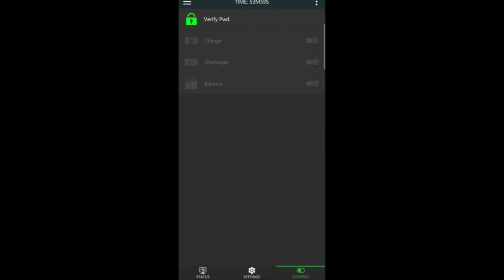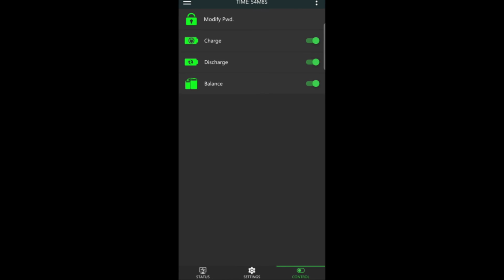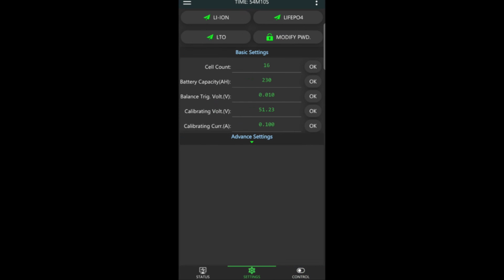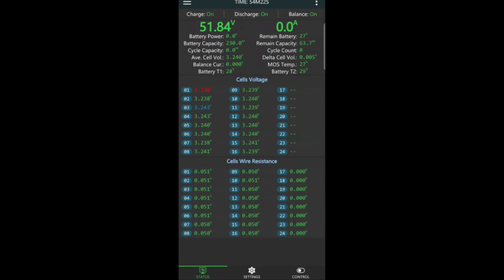So you have to log into the BMS again. The voltage is showing as 51.22, but the actual voltage is 51.84 as per my multimeter. So I will calibrate it here, and now the voltage is shown as 51.84.